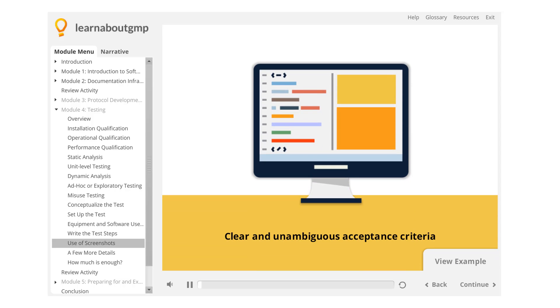For each test performed, clear and unambiguous acceptance criteria needs to be defined. This can take multiple forms. If a quantitative value is defined and if there is any tolerance, be sure to provide the range. Ideally, this is defined in requirements, but if not, it needs to be defined in the protocol. Remember that appropriate personnel review and approve the protocol, so such definition is acceptable but should be considered a last resort for specifications.